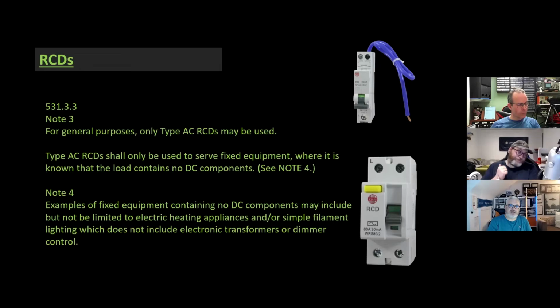Yeah, it's bad because there's not enough guidance or information for the installer to make a better informed decision, other than get a clamp meter out and start measuring. John, me and you were talking the other day about earth leakage of products - there's some great guidance out there from Schneider, but if you want to buy all of the product standards to find out exactly what the leakage is, it will cost you about 24 grand, which I don't have, to be perfectly frank.